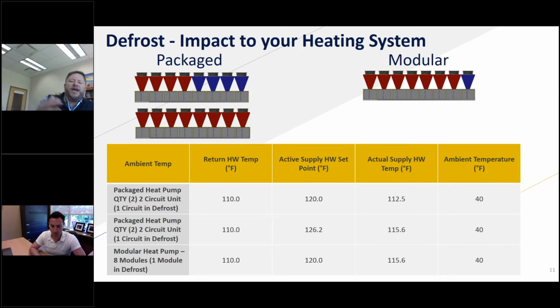So it ranges from that and gets far more sophisticated, whether it's looking at airside pressure drop across the coil, or looking at actual operation of the refrigeration system internal to the system. Typically, if you're going on that timer route, you simply run through a timer, you run as long as it says to do that, and then you switch back. If it's a little more sophisticated methodology, then there is a point at which you say, hey, I know I've gotten rid of the frost, now I can switch back. So that would take you out of defrost.